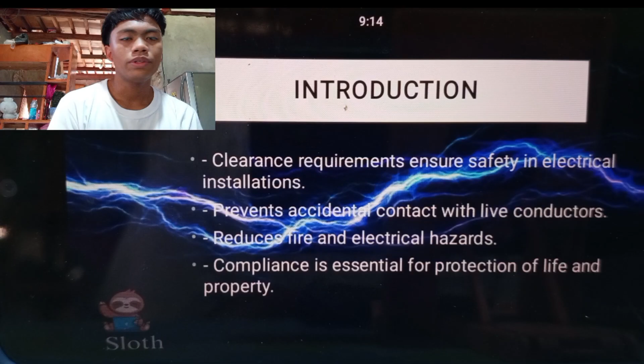Vertical and horizontal clearances. This refers to the minimum distance that unguarded or accessible wires, conductors, cables, and rigid live parts must maintain from buildings, signs, billboards, chimneys, radio and television antennas, tanks, and other installations when the conductors are at rest. It defines the concept of at rest, the minimum vertical and horizontal spatial separations from various structures.